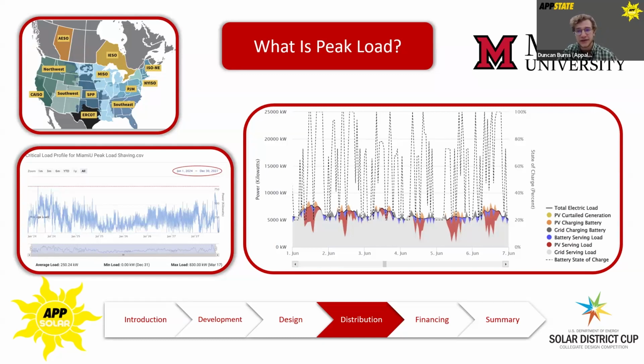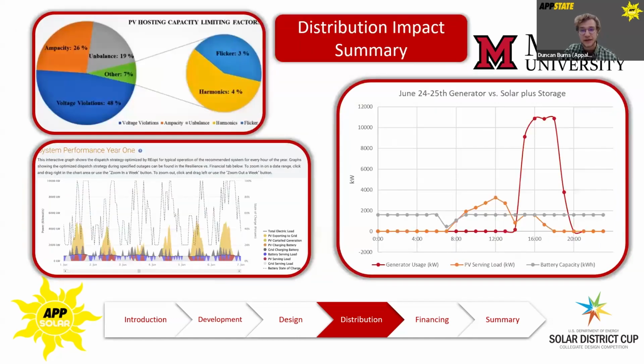The university currently mitigates their impact on the transmission infrastructure and the peak demand costs they are liable for by generating power from 2 5.5 megawatt natural gas generators on days when the utilities expect high grid demand. Unfortunately, due to the slow dispatch time of these generators, the university is financially incentivized to run their generators at maximum capacity for the full day, and this leads to high fuel costs and a massive increase in the campus's Scope 1 emissions. Looking at the graph on the right, you can see how the current natural gas generator solution is sluggish and inefficient.